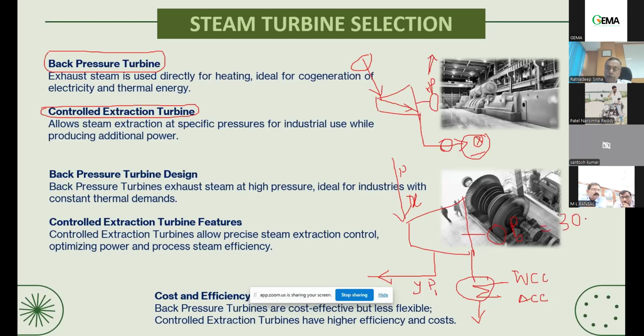Now tomorrow, if because of part load operation this power is reduced to 24 TPH, then this P1 also is going to reduce almost in the same proportion. Basically, P1 is a function of the flow rate, directly proportional to the flow rate of the main steam. So if the main steam reduces, this pressure also reduces.